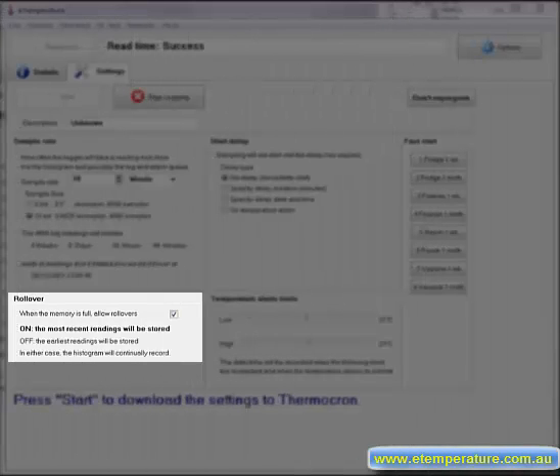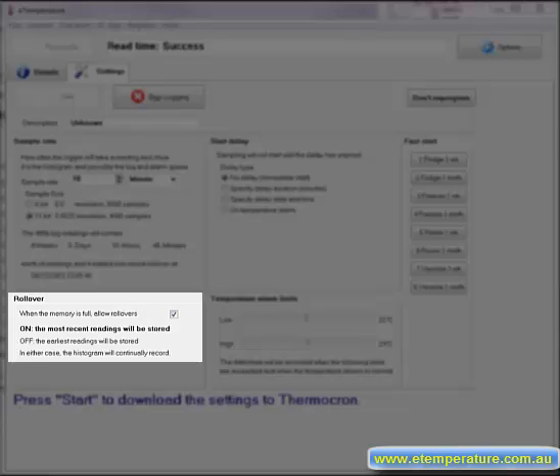The allow rollover flag is the next critical thing that must be set. The guideline for this is very simple, turn it on. This means the logger will always be running and storing results. The oldest results will be lost when the memory is filled and you will always have the most recent readings. By turning the allow rollover flag on you won't need to reprogram the logger each time you retrieve the results. Just retrieve the results and put the logger back in place. The only exception is if you are shipping something you don't control how quickly the logger will be reprogrammed. When the logger reaches its destination and the memory becomes full it will automatically stop logging. You will have the initial results always in memory.